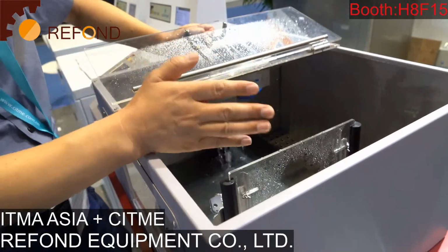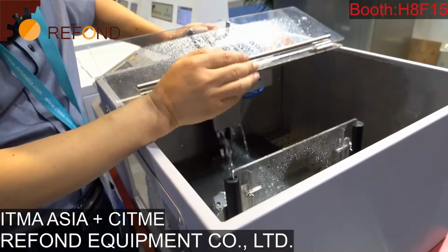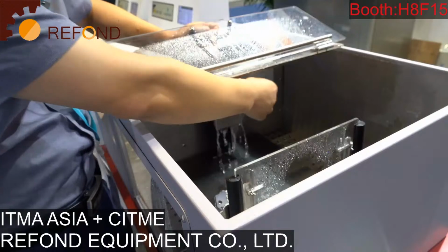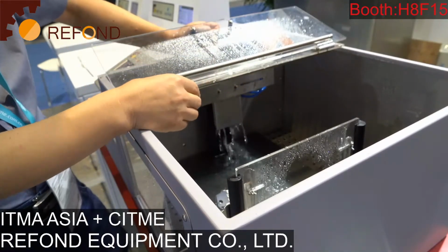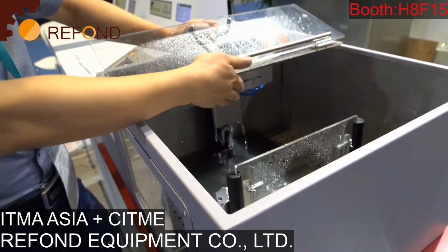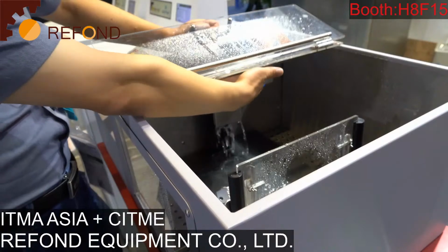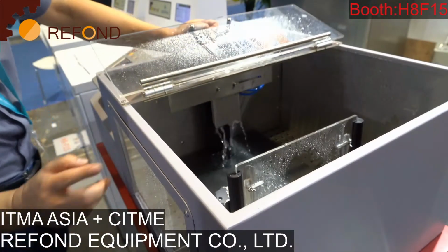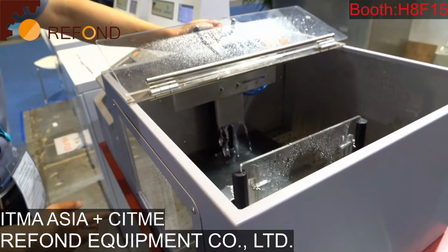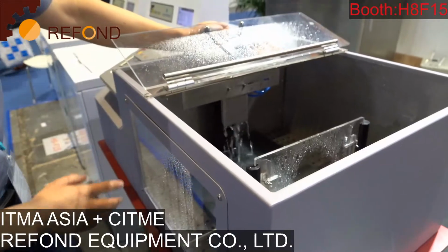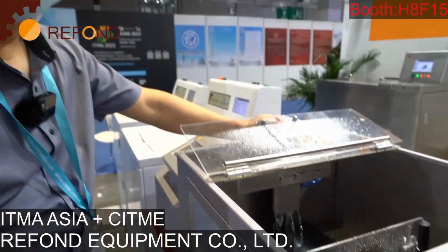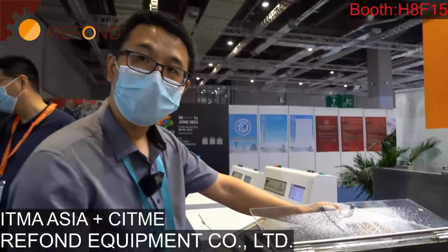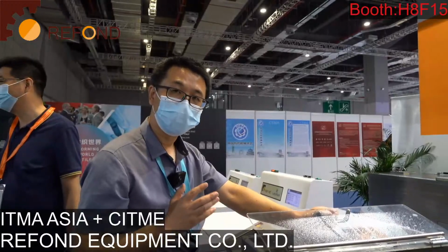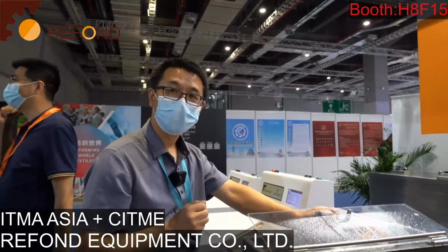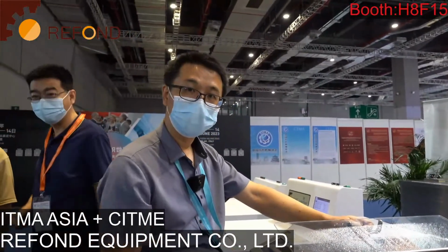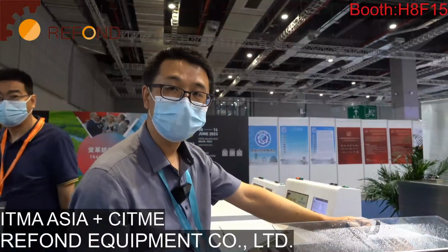But now there is no compressed air in the exhibition center, so I move it by hand. The blocking plate makes it possible for the water to circulate continuously. The continuous water circulation makes a stable pressure. So the machine can control the water pressure stably.